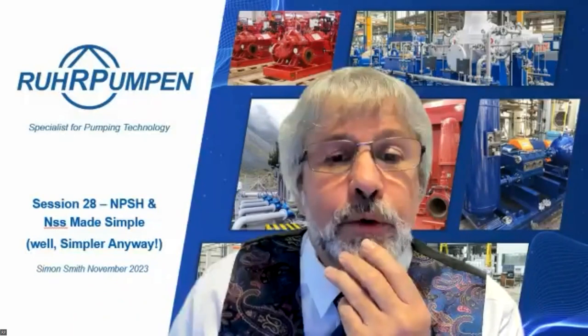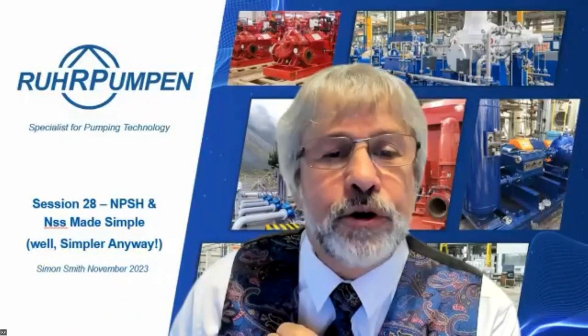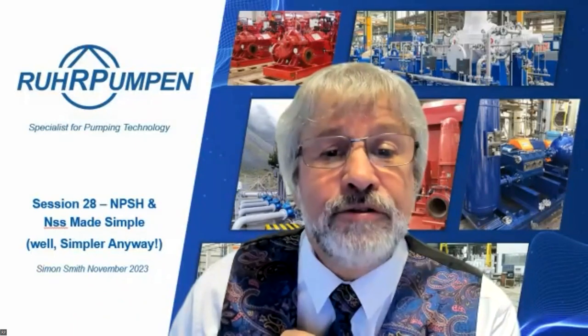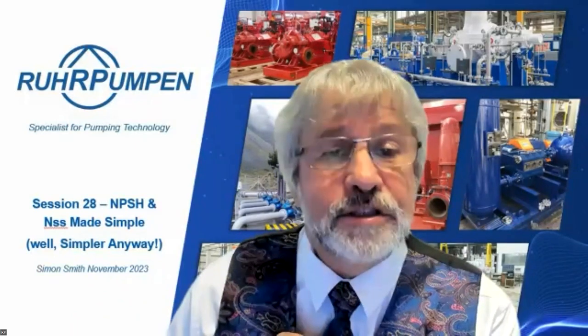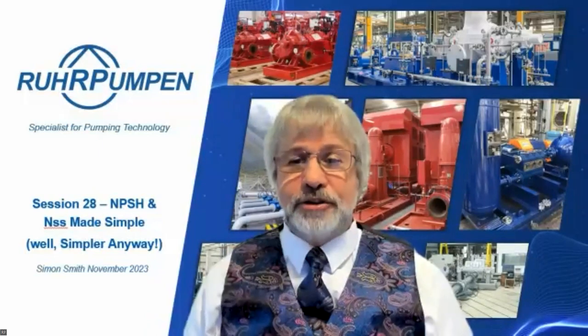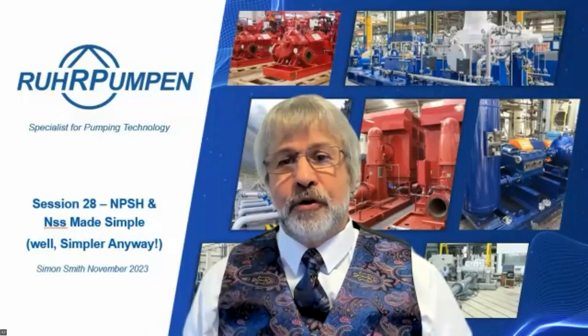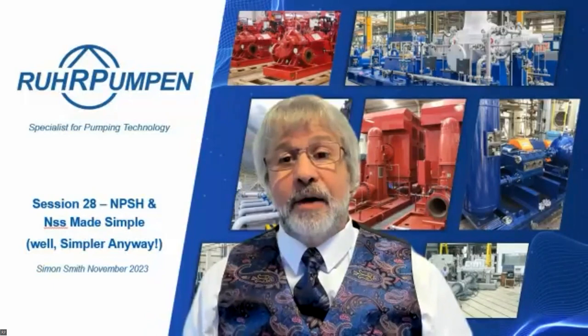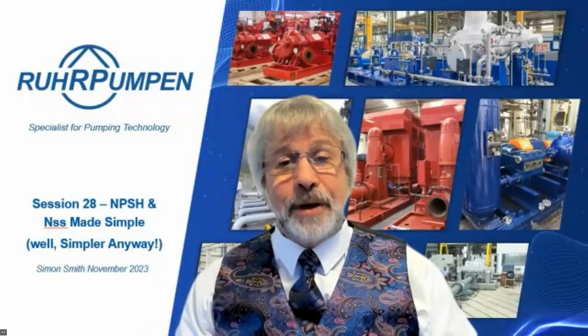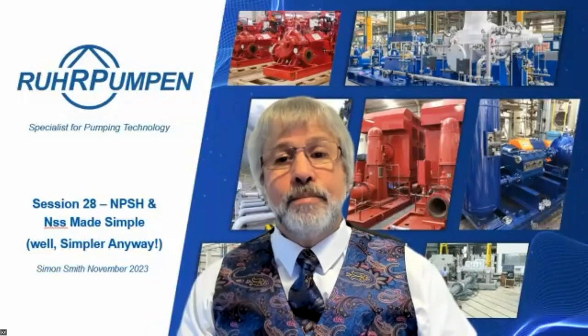Mohammed Ibrahim asks: the liquid entering the pump suction nozzle is rotated with the impeller speed - is there any effect on NPSHr values, and should this be minimized by inline guide vanes to reduce entrance losses? Yes, good point - that's exactly what our hydraulic engineers are trying to do: minimize losses as flow goes into the impeller. We use computer modeling as well as windows in the pump to see what is actually happening and achieve absolutely optimal flow through the pump with minimum losses.